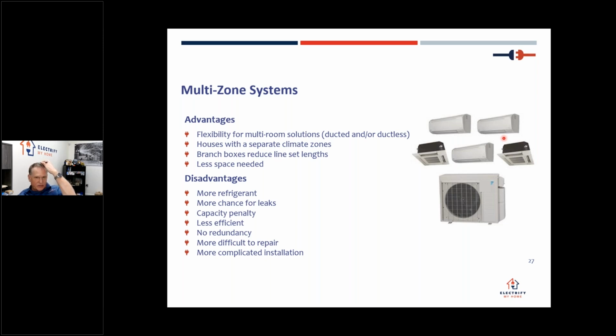There are some downsides to these. They need a lot more refrigerant. Things are hyper-concentrated on the refrigerant these days. These units take a lot more refrigerant. And because there's a set of pipes that connect each one of these units to the outdoor units, there's way more chance for leakage. The units have to combine the capacity of all of these in the outdoor unit, so there's a bit of an energy use penalty.